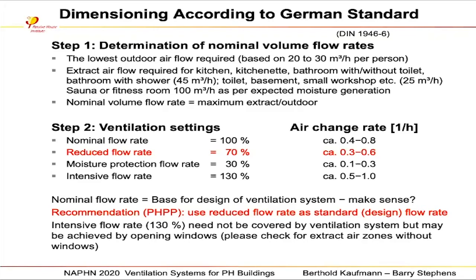Well, but what you can see, the intense flow rate, maybe for a party, or if there are very many people in a classroom or a meeting room, this intense flow rate need not be covered in any way by the ventilation system, but this can be covered by window ventilation. So in addition of open windows. And this is what we called before this hybrid ventilation. And from our point of view, it's a quite good compromise to go for.